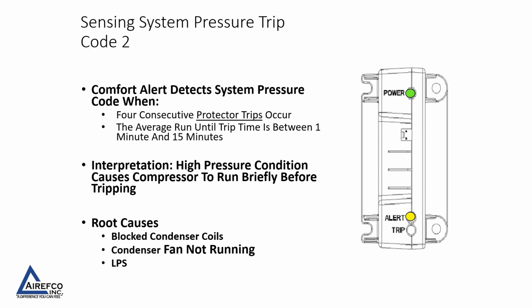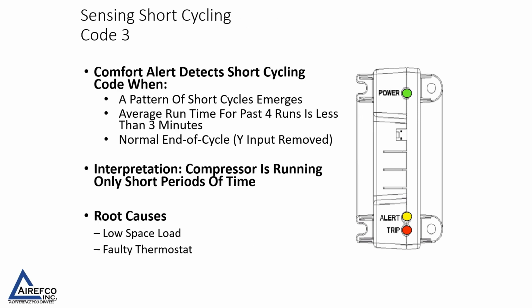If your yellow LED is flashing 2 times to alert you to a problem, the code 2 tells you that the Comfort Alert has detected system pressure codes. 4 consecutive protector trips have occurred. It could be a high pressure condition causing the compressor to run briefly before tripping. So if you see the amber LED flashing 3 times, this means that the Comfort Alert device has sensed a short cycling pattern, which means the compressor is running only for short periods of time. And it gives you some root causes that you could look at to resolve the issue.